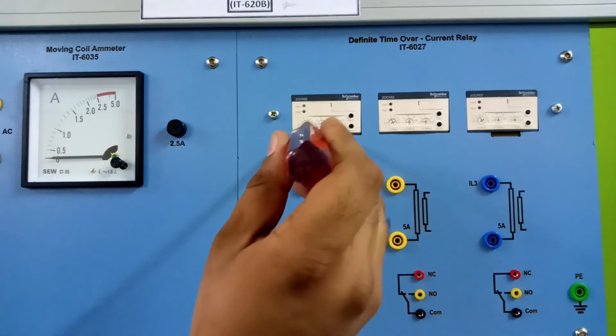So now I'm going to set the timer. First of all, the load is around 0.5. So there you go, I have set 0.5 for all the three relays. So now this is on 0.5. Again, this setting has to be done precisely because all three relays should be at the same value.